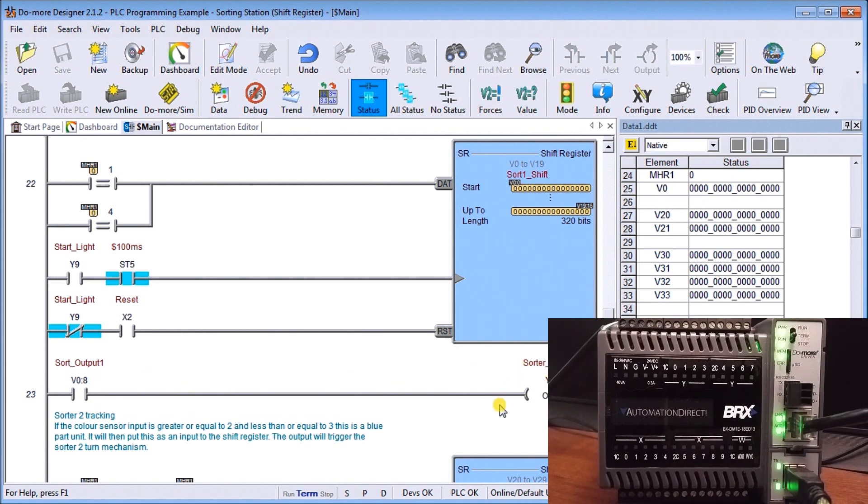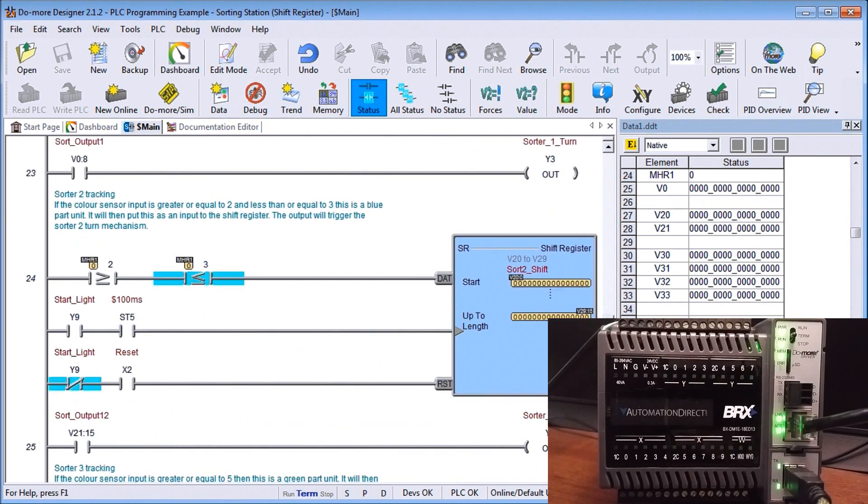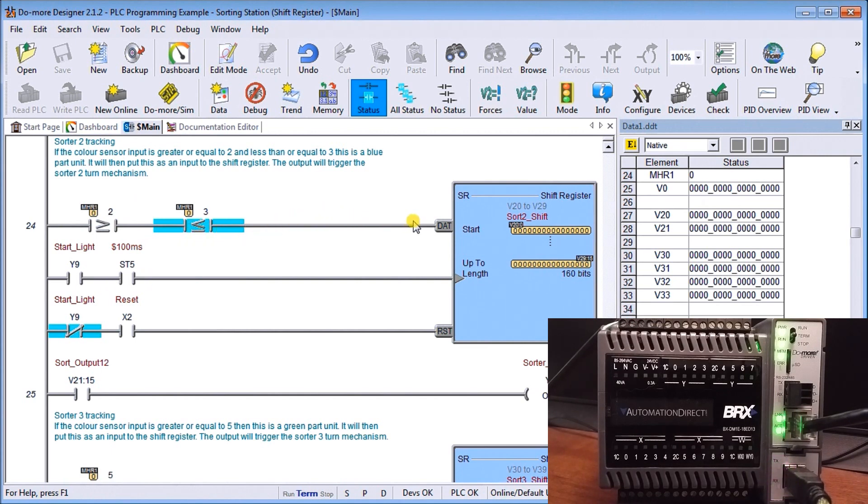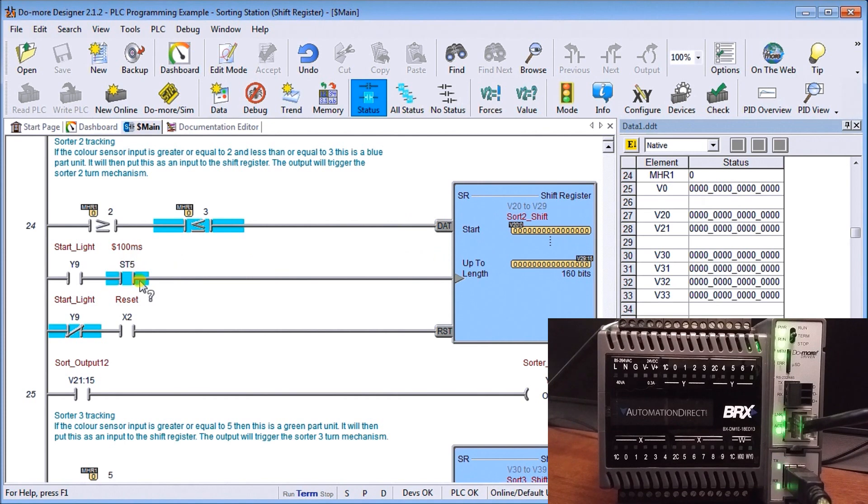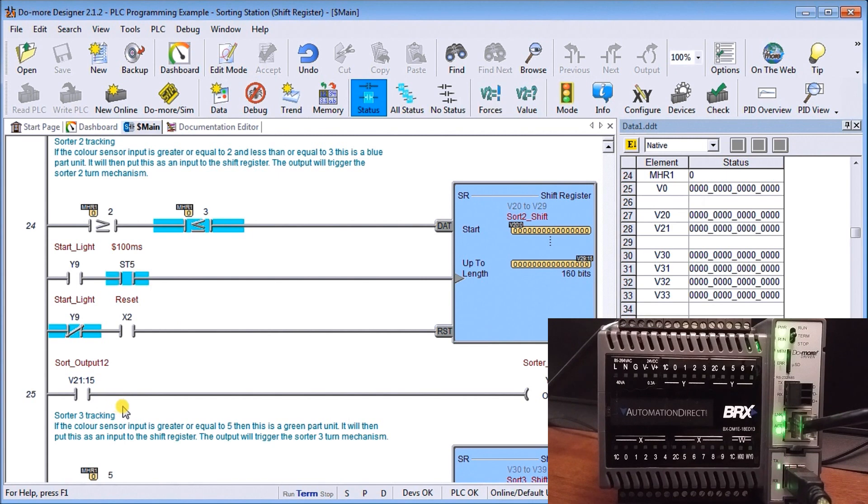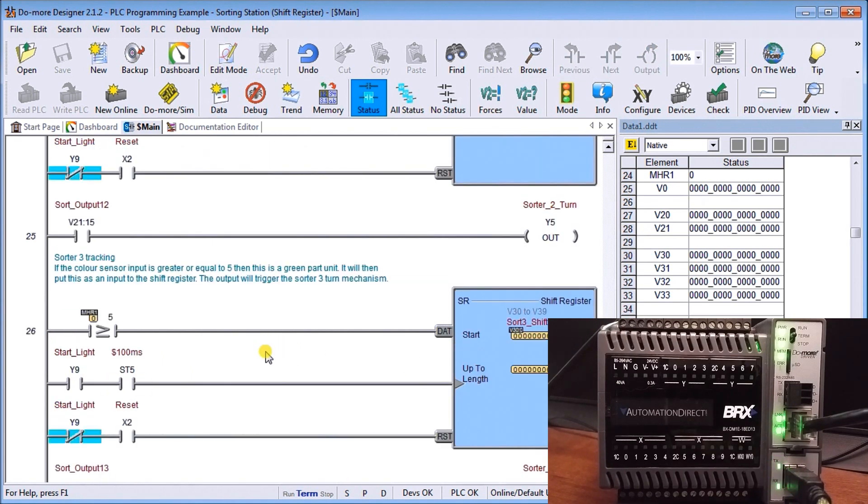We do the same thing with our sort tracker number two. In this case, it has to be greater than or equal to two and less than or equal to three. It will provide data to our shift register from V20 to V29. Again, we use the system pulse bit flag to track what's happening. All three of these chutes operate off the same pulse bit.